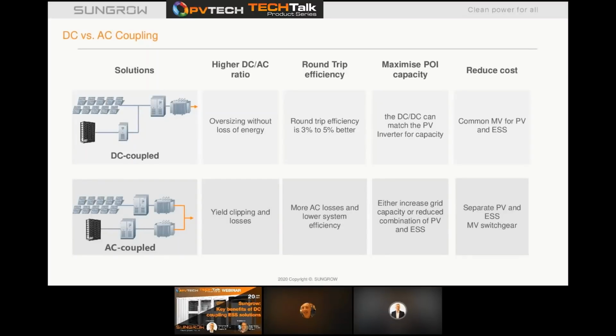So to give a brief comparison of the solution, I've highlighted the main key differences of a DC coupled system against an AC coupled system. To summarize, the DC coupled system allows you to increase the DC-AC ratio of the PV system without fear of loss of yield due to clipping. Greater cost savings can be achieved by reducing the number of MV stations required. This also results in greater system efficiency, which in turn leads to project savings on the civils, the labour, the commissioning, and the O&M costs too.